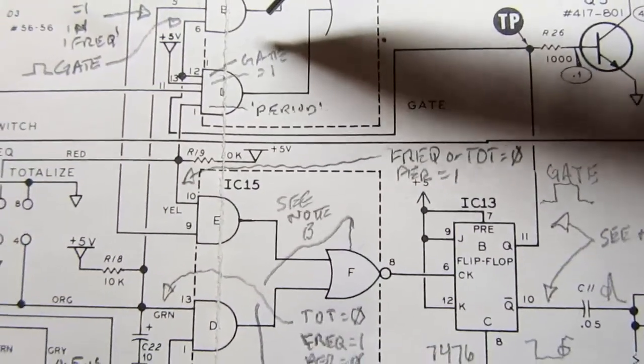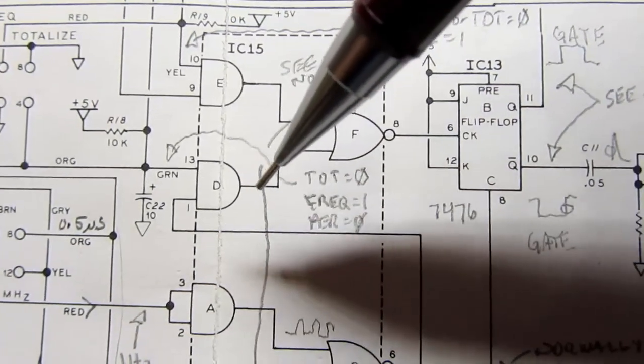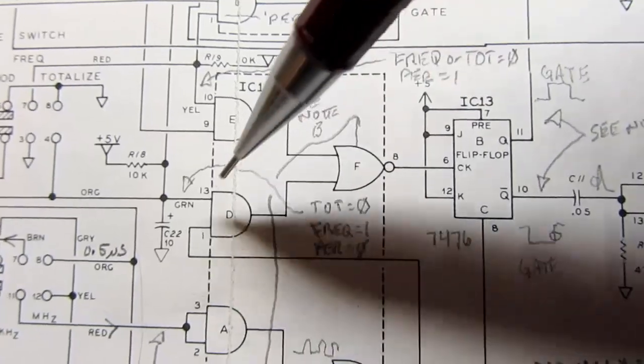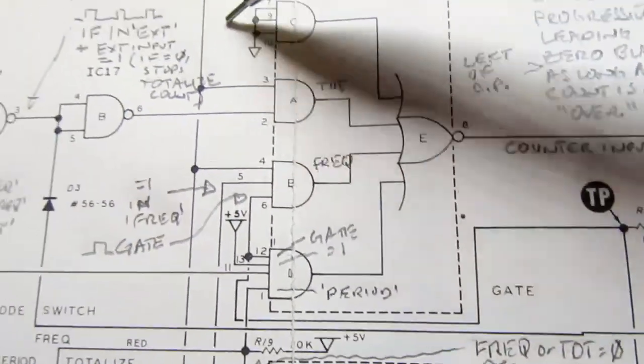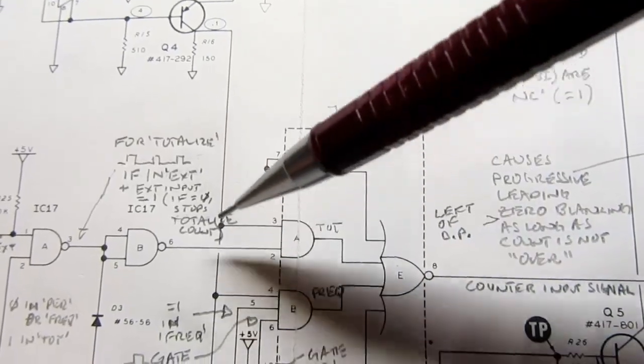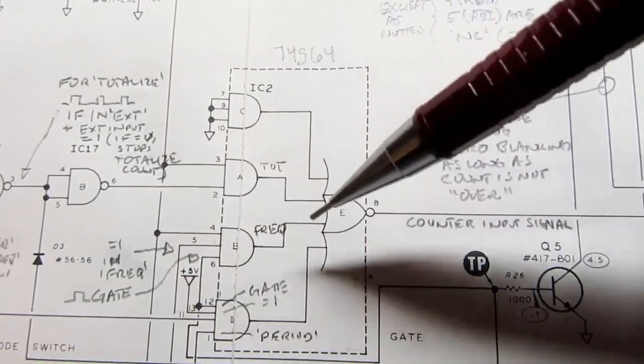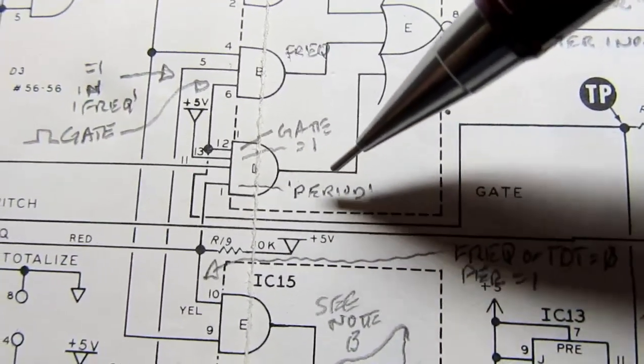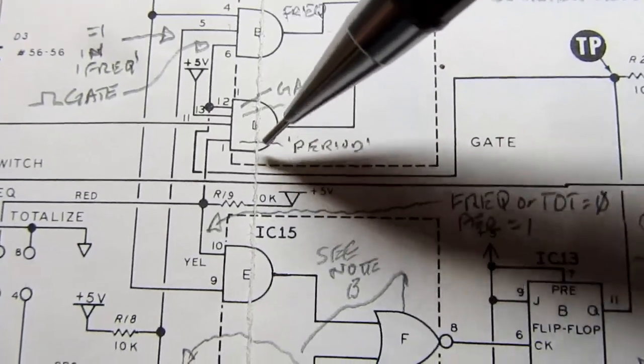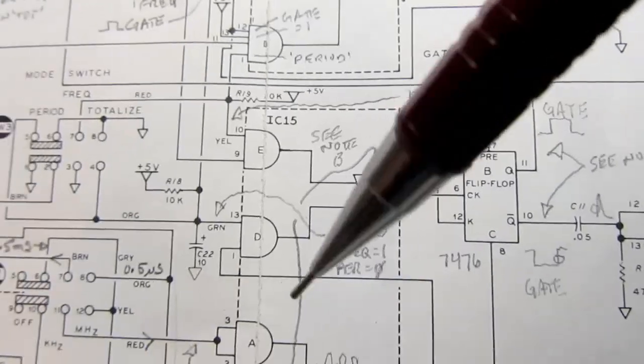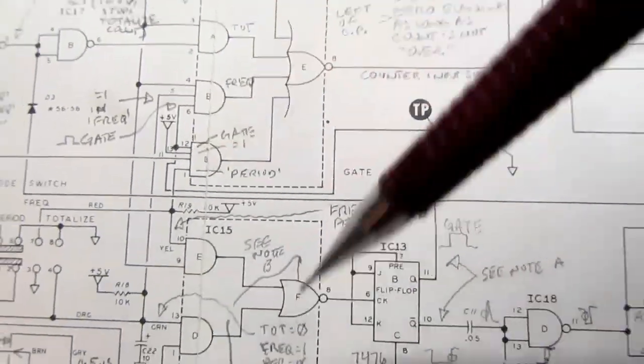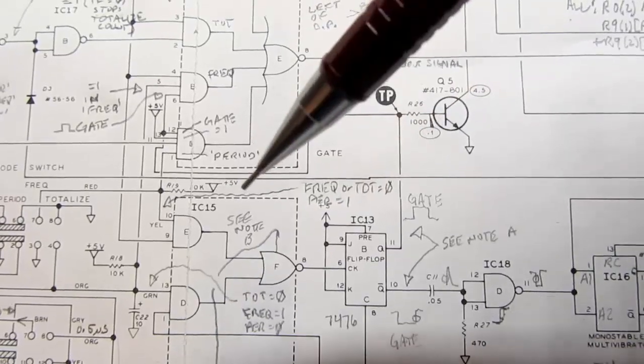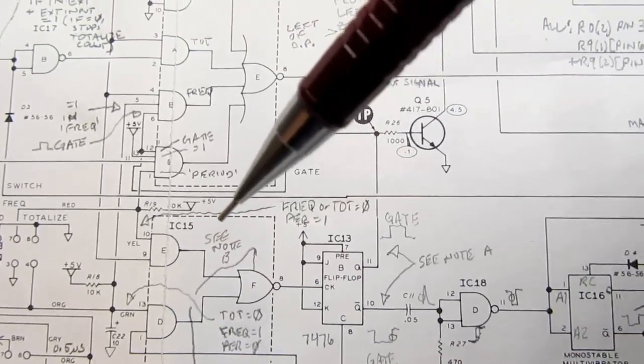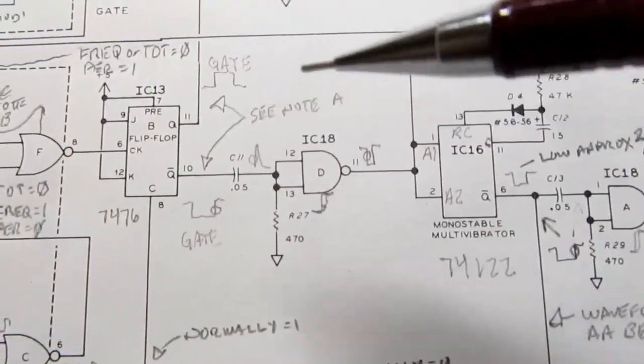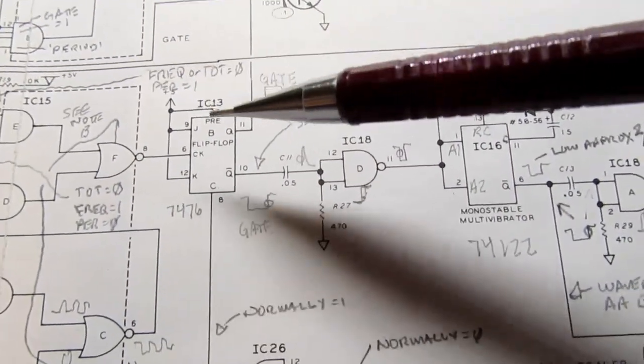If you're in frequency counter mode, this part of the logic picks the master clock as the source of the gate, and up here it picks the output of the signal conditioning circuit as the signal that goes through the counters. If you're in period mode, this should be based on the master clock, and in fact it is. So these two ICs are where that reversal of gate and input sources is accomplished. I know it's kind of hard to see here and I'm going kind of fast, but...